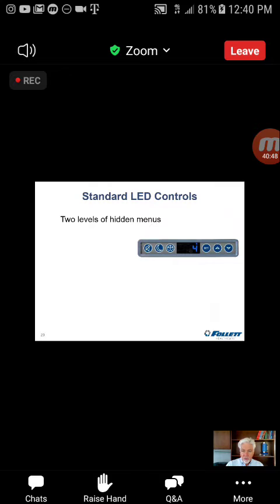There are 2 levels of hidden menus to access higher functions in the control system. To access these, now this rule applies to all Follett equipment, even some older control styles from a different vendor, it is always the set or enter button and the arrow closest to it. That's the easiest way to remember it. I can never remember up, down. I remember positionally. Set button and the arrow closest to it.